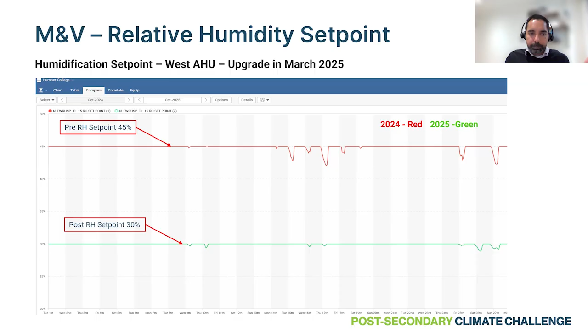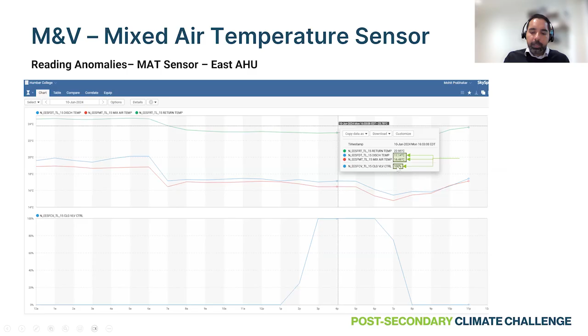There was an issue with the mixed air temperature sensor, which was identified as part of the trend analysis. The mixed air temperature was 16.46, and the discharge was 17.14, even with the cooling valve 100% open. So the mixture was lower than the discharge with the cooling on, which tells you there's an issue with the mixed air temperature sensor.